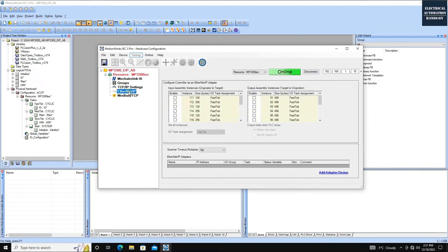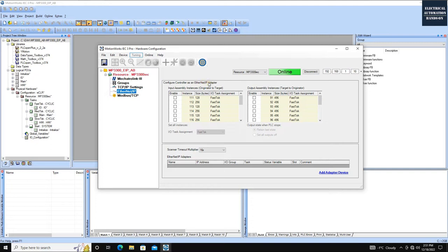After rebooting, click Connect. This time the comparison window doesn't appear because the offline and online configurations match. Go to the Ethernet section — there are two windows here. Be careful: the top window is the configuration for the MP3300 running as Ethernet IP adapter. The bottom window is for when the MP3300 runs as Ethernet IP master, where you can configure external adapter devices. In this case, since the MP3300 is running as Ethernet IP adapter, we can ignore the lower master window.